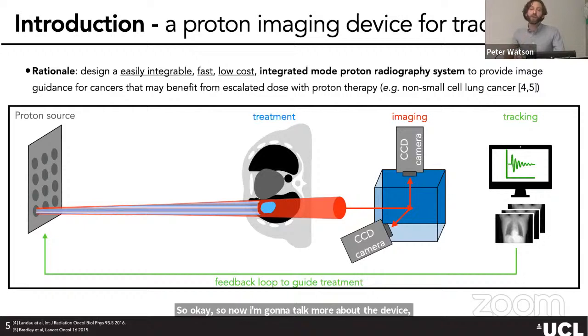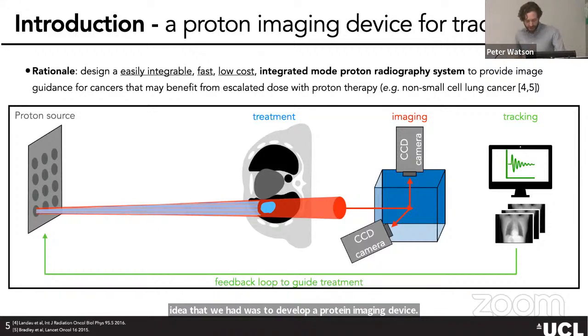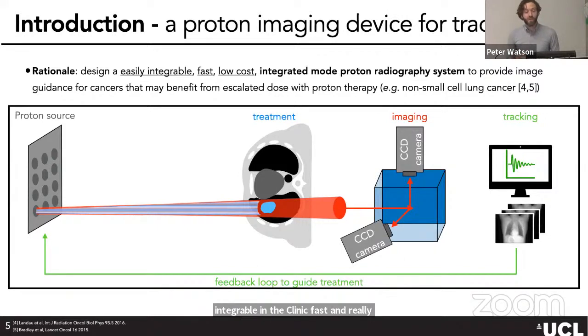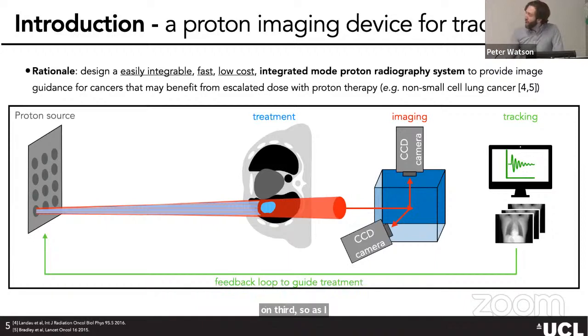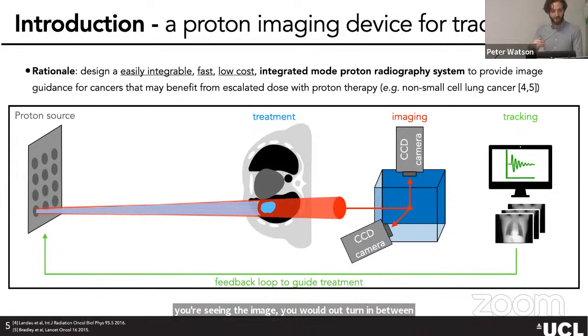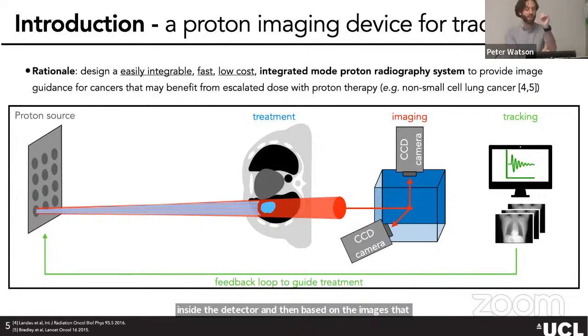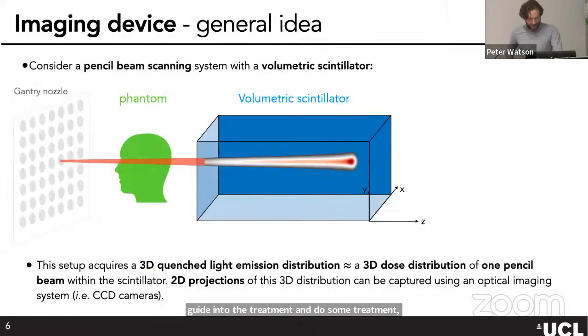The idea of our project was to develop a proton imaging device specifically for tracking for lung cancer — an easily integrable, fast, and low-cost proton radiography system to provide image guidance for cancers that might benefit from escalated dose in proton therapy, such as non-small cell lung cancer. The system alternates between treatment and imaging mode by changing the energy of the source, then uses feedback to guide treatment adaptation through gating or other techniques.